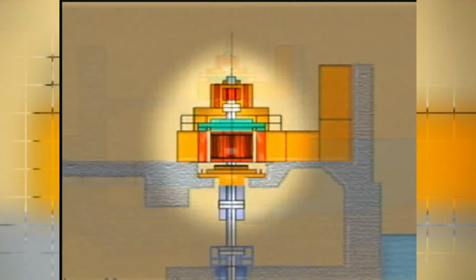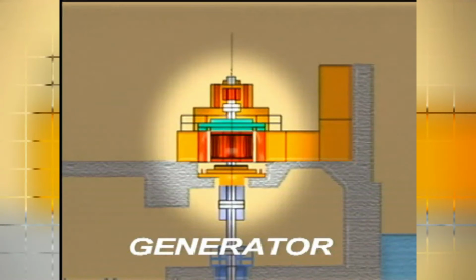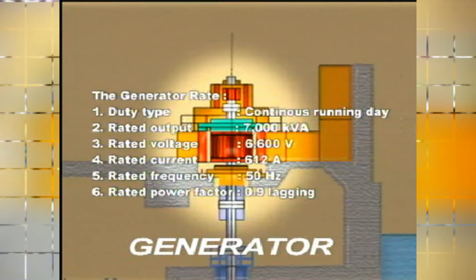Type and rating. The generator is a three-phase, vertical shaft, conventional or suspended type synchronous generator with a salient pole revolving field. The cooling system is the outlet duct air ventilation type. The generator is rated as follows. Duty type, continuous running duty. Rated output, 7,000 kilovolt-amperes. Rated voltage, 6,600 volts. Rated current, 612 amperes. Rated frequency, 50 Hz. Rated power factor, 0.9 lagging.